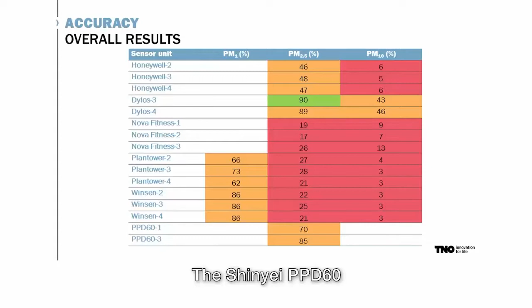And then some other sensors, yeah, it's doing a reasonable job, but not that well. 50% for the Honeywell. The Shinyei PPD60 is a bit higher, but keep in mind we calibrated during the ramping experiments, so it's calibrated with this dust. For PM10, you really see that the accuracy drops quite dramatically for all the sensors. For the Dylos, it's still the best, 43 and 46, but for the others, it's below 15%. So it really gives a high underestimation.